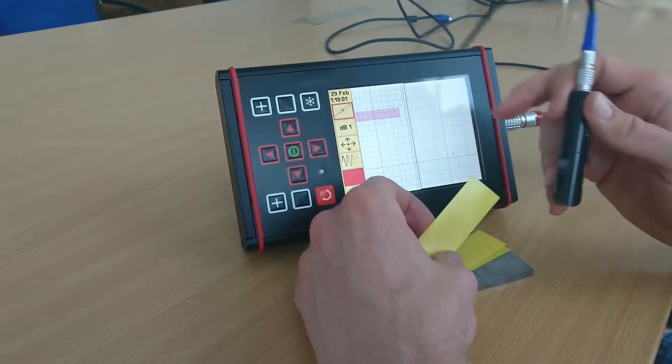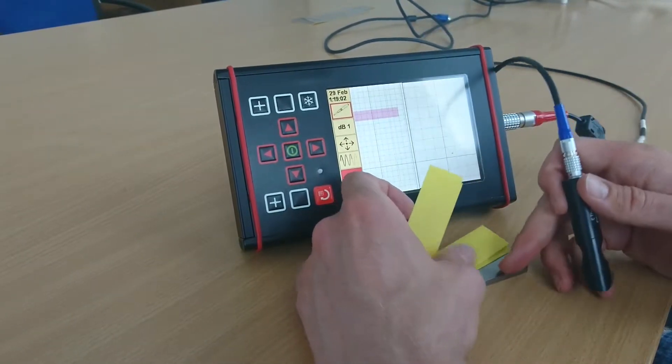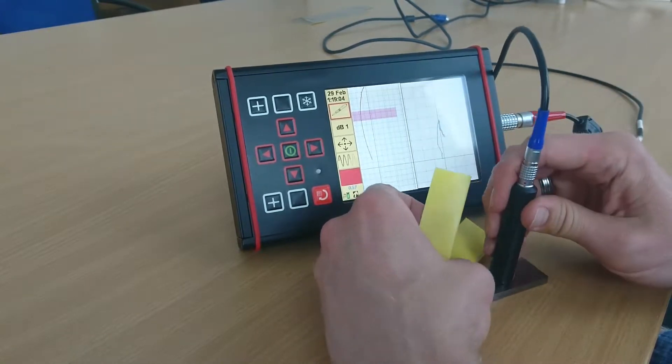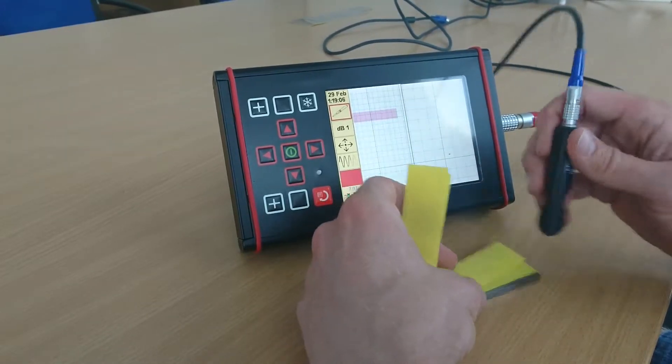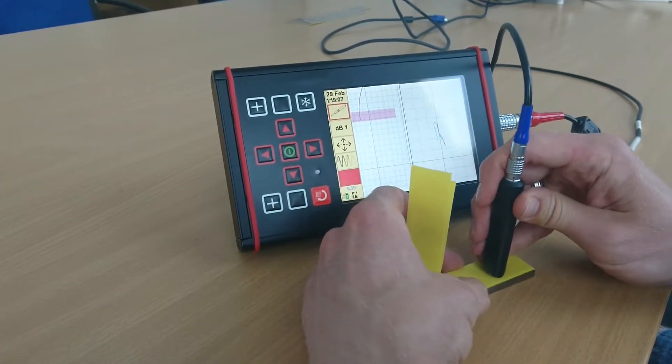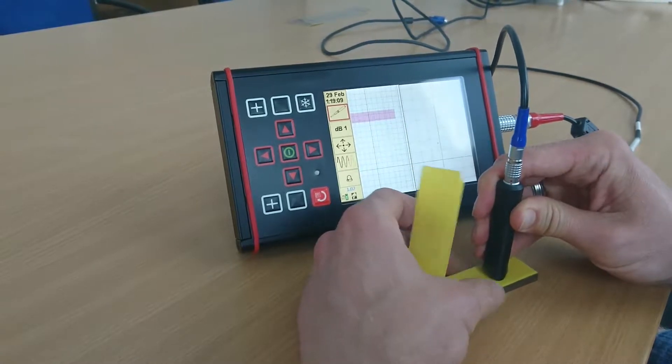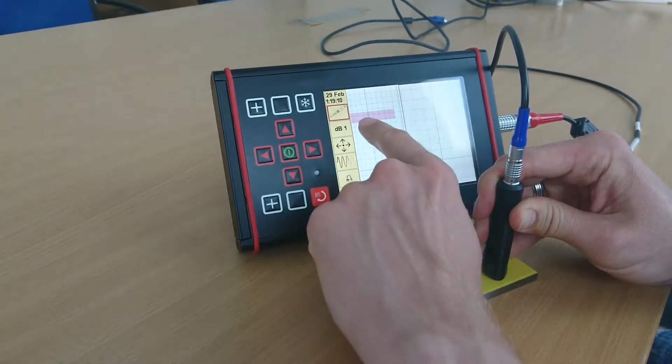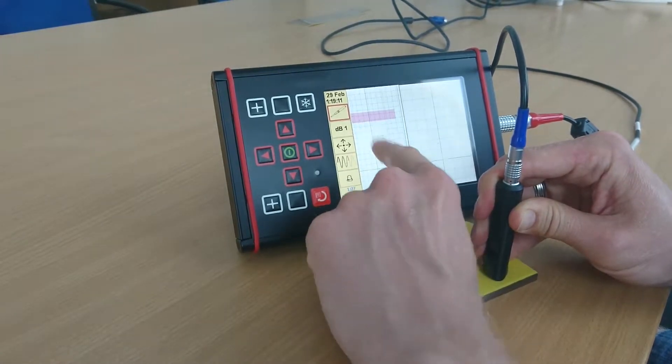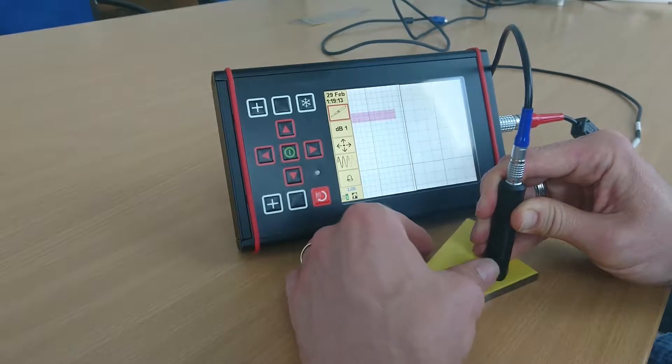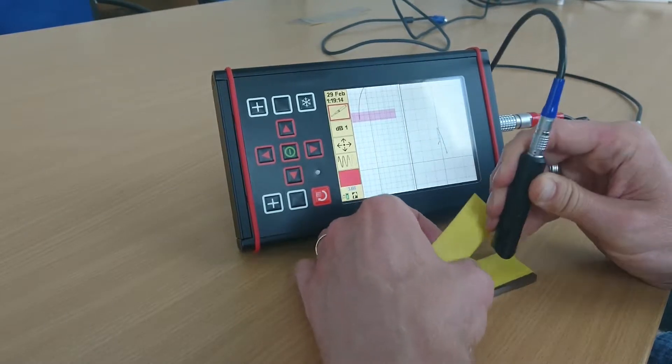If I have two shims, one millimeter or about one millimeter, we're just inside the safe zone which we set up as between one and 1.5.